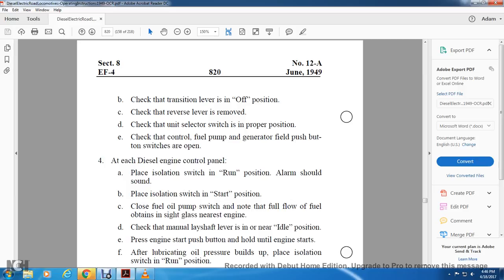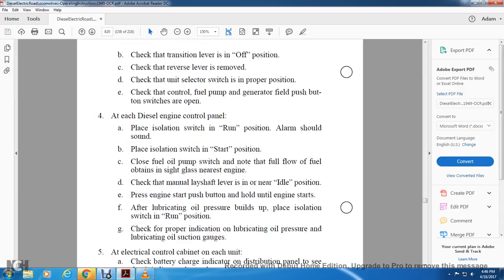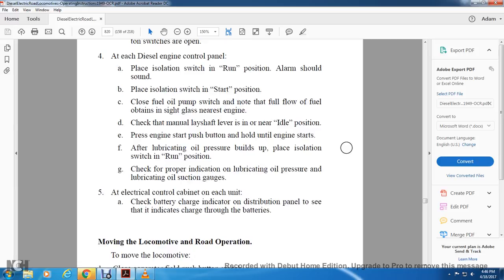Press the engine start push button. Hold until the engine starts. After the lubricating oil pressure builds up, place the isolation switch in the run position. Check for proper indication on the lubricating oil pressure and lubricating oil suction gauges.